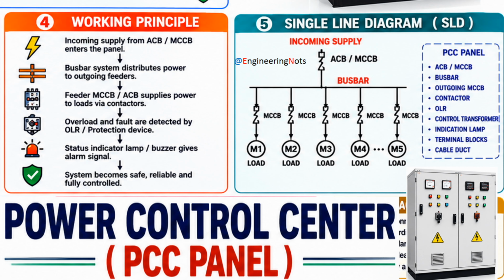Think of the air circuit breaker as the main gate of the entire electrical system. As long as this breaker is closed, electrical power can enter the panel. If a serious fault occurs, this breaker opens immediately and disconnects the incoming power. After passing through the air circuit breaker, the electrical power reaches the copper bus bars. These bus bars distribute power evenly to every outgoing circuit inside the panel.